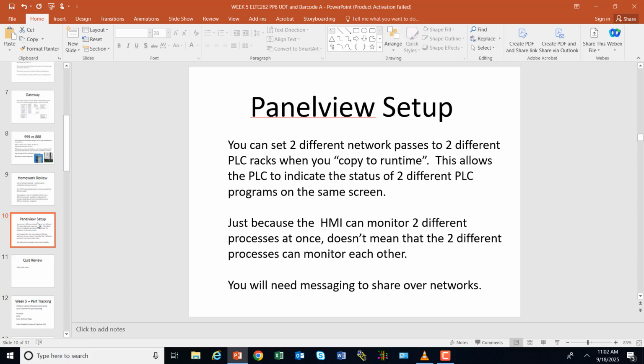Panel view setup. This is interesting. We had one of the students messing with this. When you set up your panel view, you can set up two network passes to two different networks. When you run your link setup, your FactoryTalk Link setup, you can install two connection pass-throughs to PLC racks on different networks. And then when you click copy to runtime, it will allow the PLC to show the status of two different PLC programs on the same screen.